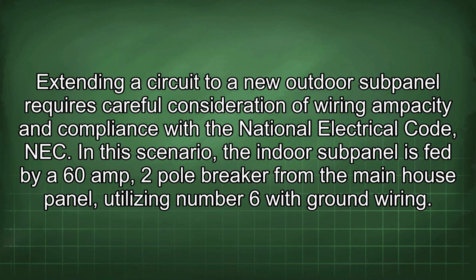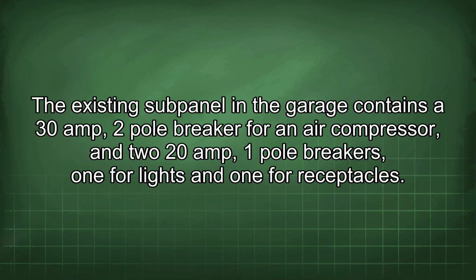Extending a circuit to a new outdoor subpanel requires careful consideration of wiring ampacity and compliance with the National Electrical Code (NEC). In this scenario, the indoor subpanel is fed by a 60-amp 2-pole breaker from the main house panel, utilizing number 6 with ground wiring. The existing subpanel in the garage contains a 30-amp 2-pole breaker for an air compressor and two 20-amp 1-pole breakers, one for lights and one for receptacles.